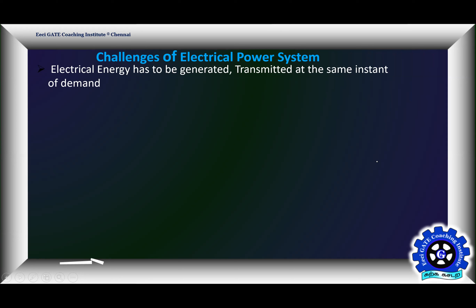Maintaining the voltage and frequency fluctuations of the power system within the operating range while meeting the load fluctuation is the biggest challenge. To provide quality electrical energy, our voltage fluctuation should be plus or minus 6% of the nominal voltage, and frequency fluctuation should be plus or minus 1% of nominal frequency. Maintaining this within limits while meeting the fluctuating load is the biggest challenge of the electrical power system.